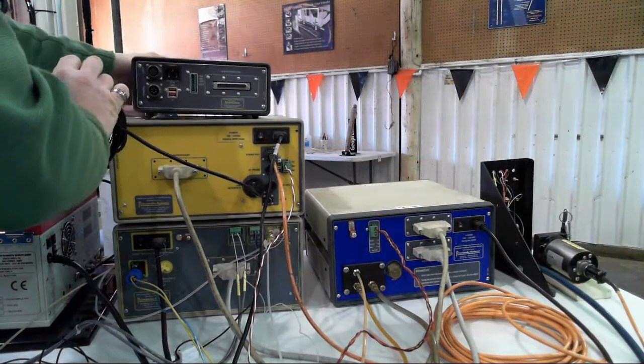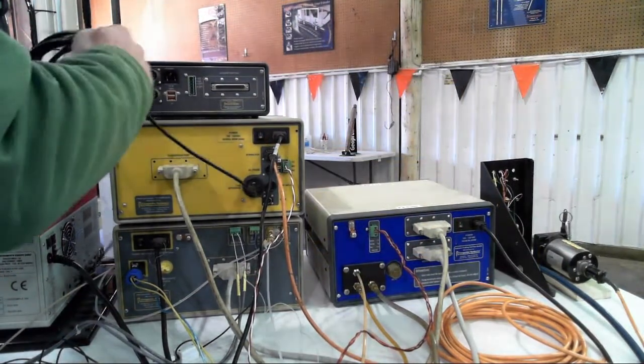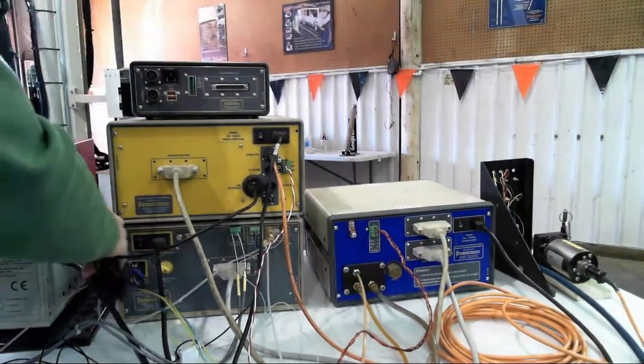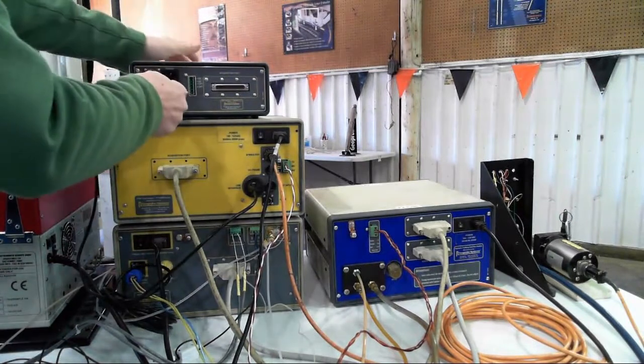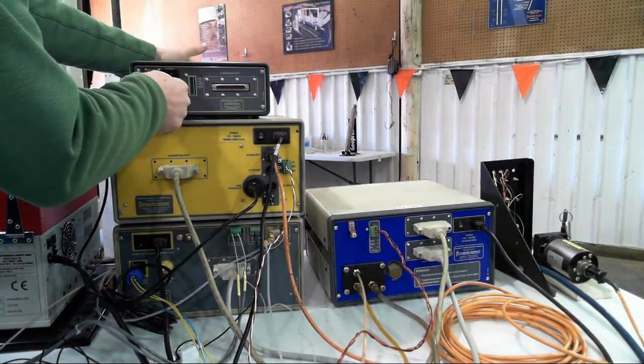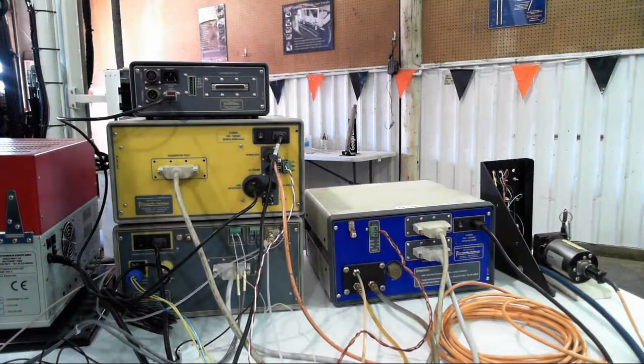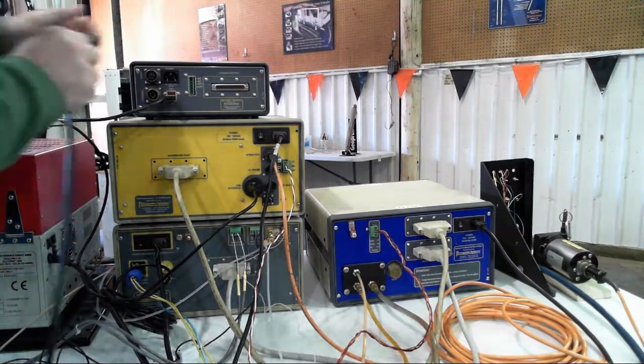The USB cable that was connected to the field laptop is now going to get inserted into either of the two USB receptacles on the back of the OIP interface. I will also then add the power cord to the OIP instrument.